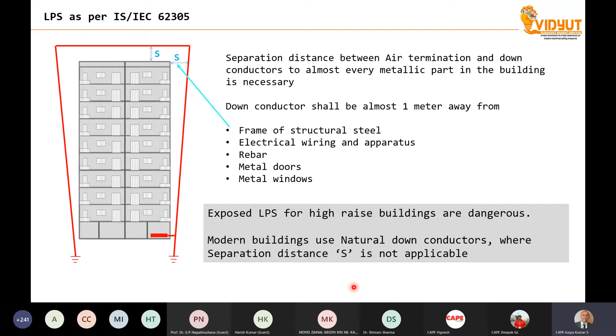Use the steel rebar or natural components for the purpose of lightning protection. This is a small introduction to what exactly the Indian standard says. The Indian standard says there shall be a grid at the top, with possibly a few rods depending on your roof. Then there are several down conductors, an earthing system, and you have to make an equipotential bonding system. You have to have SPDs and so on.